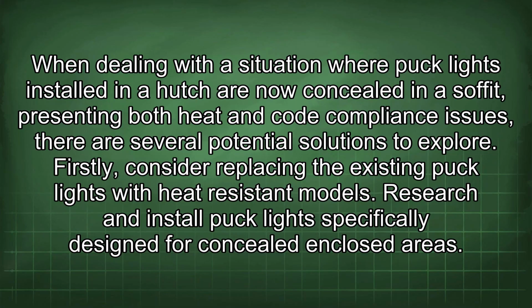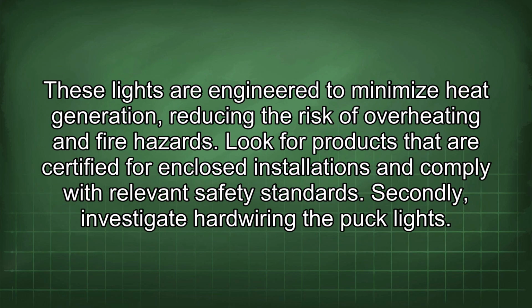When dealing with a situation where puck lights installed in a hutch are now concealed in the soffit, presenting both heat and code compliance issues, there are several potential solutions to explore. Firstly, consider replacing the existing puck lights with heat-resistant models. Research and install puck lights specifically designed for concealed enclosed areas. These lights are engineered to minimize heat generation, reducing the risk of overheating and fire hazards. Look for products that are certified for enclosed installations and comply with relevant safety standards.